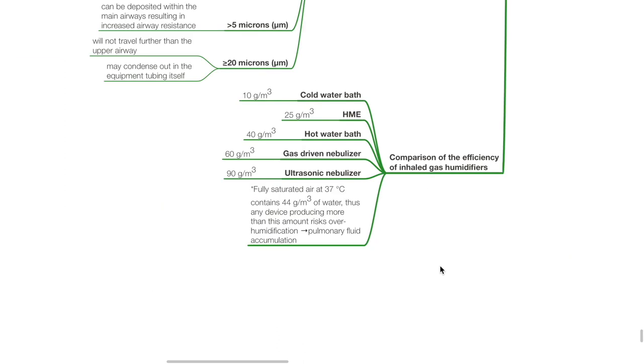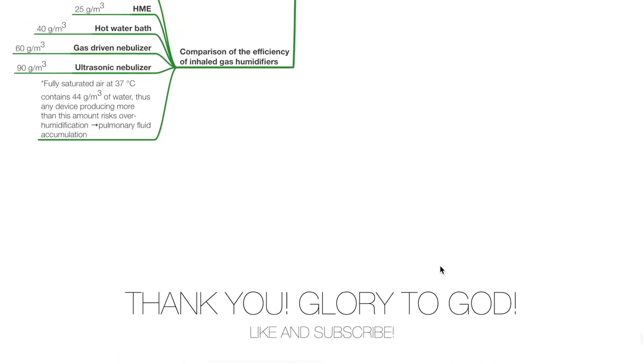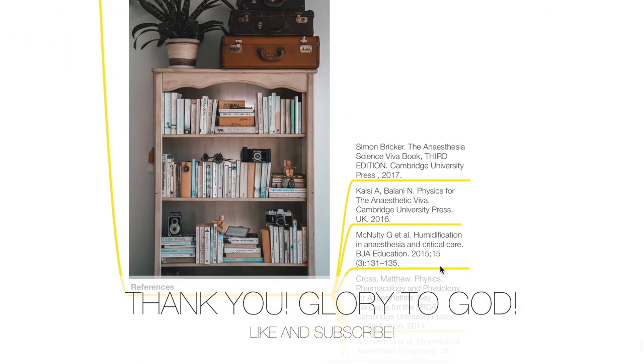Comparison of efficiency of inhaled gas humidifiers: cold water bath 10 g/m³; HME 25 g/m³; hot water bath 40 g/m³; gas-driven nebulizer 60 g/m³; ultrasonic nebulizer 90 g/m³. Fully saturated air at 37°C contains 44 g/m³ of water. Any device producing more than this amount risks overhumidification and potentially causes pulmonary fluid accumulation. These are the references. Thank you.